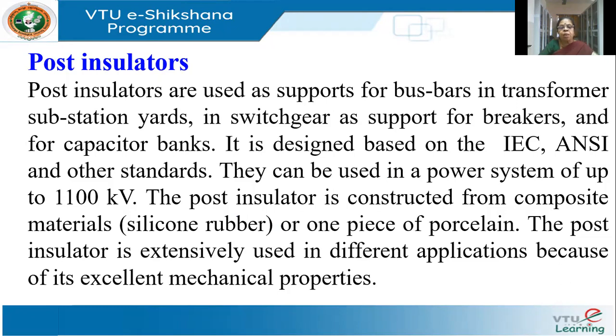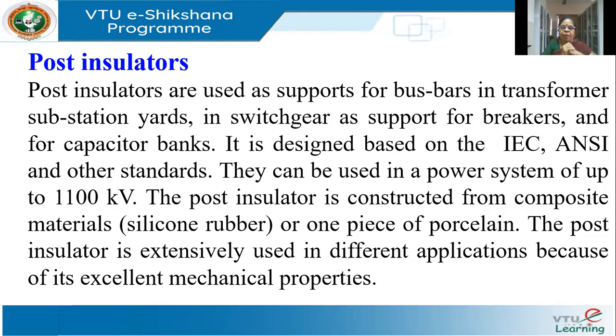These post insulators are designed based on the IEC and other standards and they can be designed up to 1100 kV. They are composed of a silicone rubber or one piece of porcelain — there is a single piece. They have a wide variety of applications because of their mechanical properties.